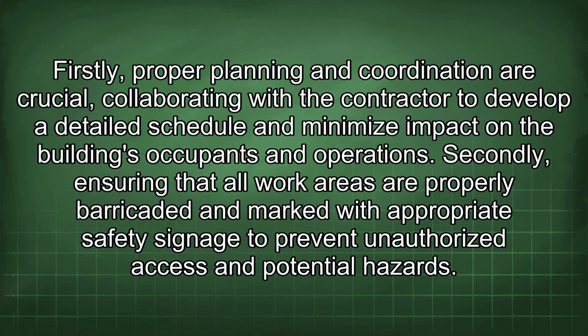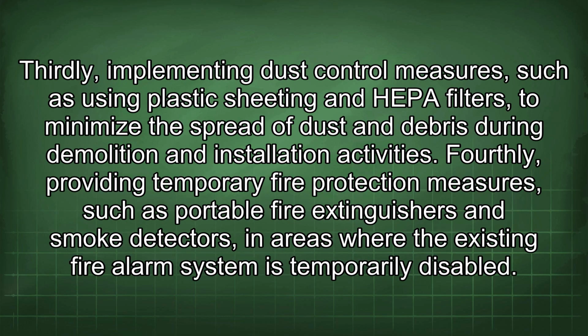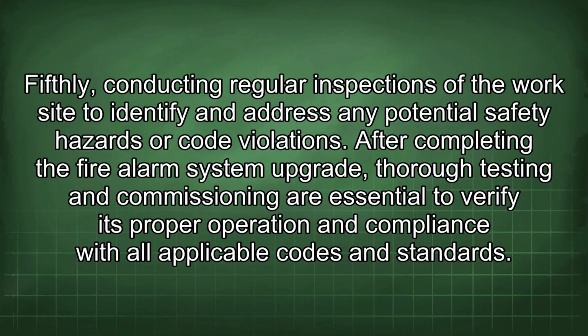Secondly, ensuring that all work areas are properly barricaded and marked with appropriate safety signage to prevent unauthorized access and potential hazards. Thirdly, implementing dust control measures, such as using plastic sheeting and HEPA filters to minimize the spread of dust and debris during demolition and installation activities. Fourthly, providing temporary fire protection measures, such as portable fire extinguishers and smoke detectors, in areas where the existing fire alarm system is temporarily disabled. Fifthly, conducting regular inspections of the work site to identify and address any potential safety hazards or code violations.